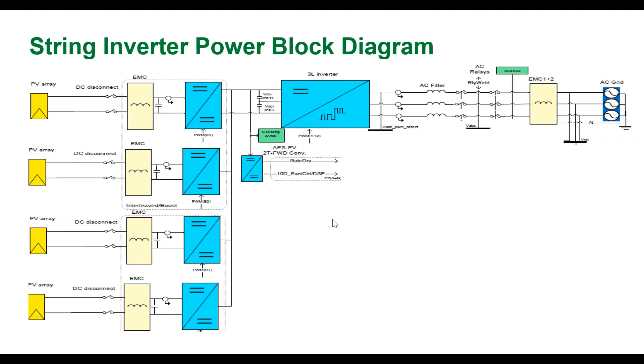Like, when your grid R phase is at positive max, your inverter R phase should be at positive max. That's when you should close the relay. So the relay closing will be synchronized with your reference signal and your PWM signal, so that everything is in sync at the right time. Your relay will close so that there will not be any circulating current and the parallel operation will be successful. So that's the block diagram of the inverter.